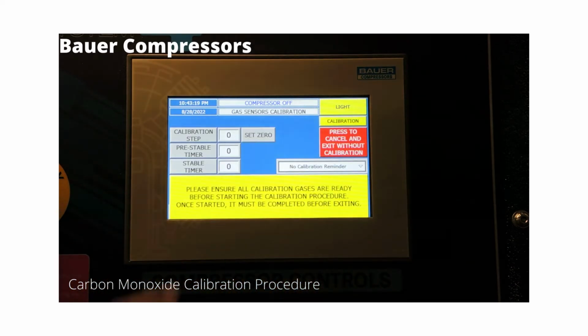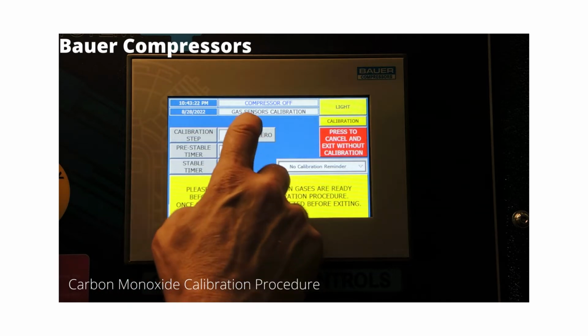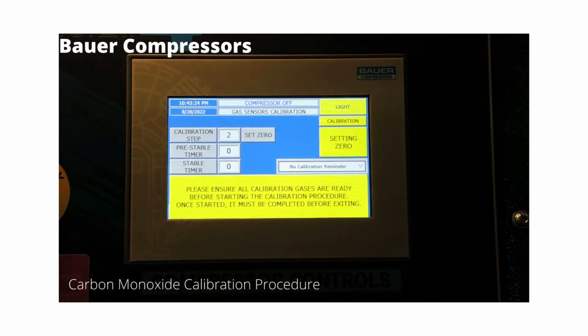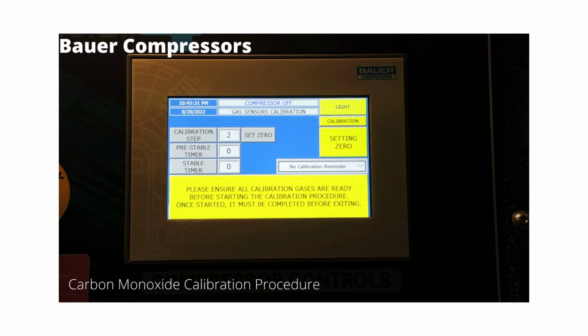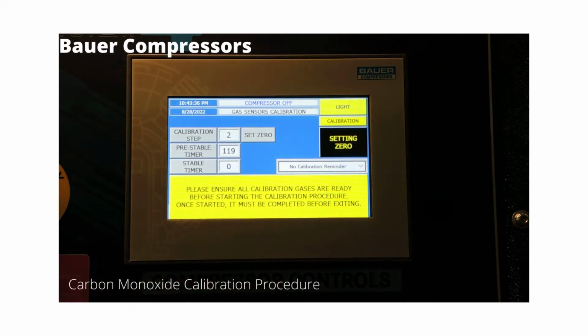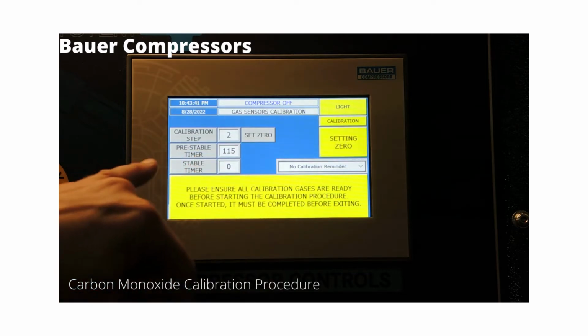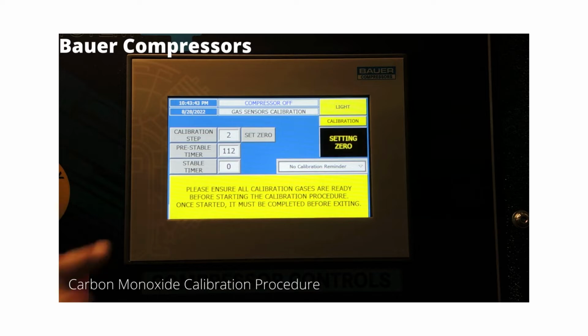So I'm going to push to calibrate. Calibration step, I'm going to hit set 0. Sometimes it will skip over and go to set span. You just need to hit set 0 again. Set 0. Once you see the pre-stable timer counting down, it's going to count down for 2 minutes, then it's going to go through a stable timer, and we're setting the 0. So I'm going to go ahead and turn the video off and catch up when we get closer.